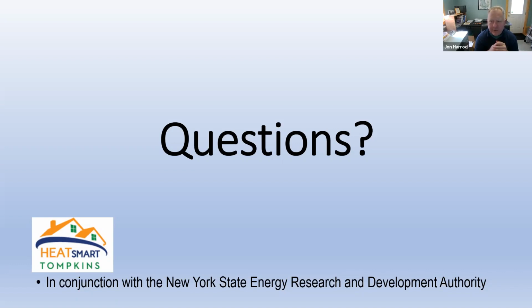You also need to talk to people about the fact that they're used to fossil fuel furnaces that could deliver 140, 150 degree supply air, while heat pumps deliver much lower supply air temperatures, typically 110 to 115 degrees. So it feels different, and it may take some getting used to. That's why it's really important to have these conversations with homeowners, to let them know this is going to feel different, and to anticipate some of the concerns.